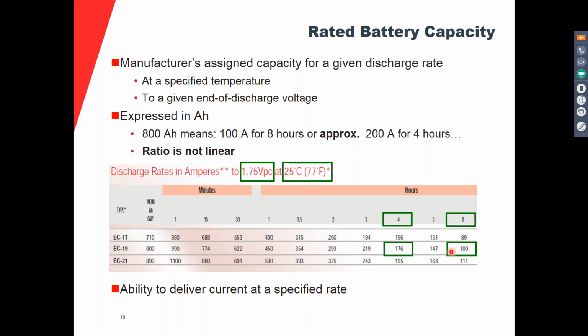You can see here with this example, for 8 hours, it can deliver 100 amps. So that will be 800 amp hours. However, for 4 hours, it can only deliver continuously 176 amps, which is less than a total of 800. So the tables have to be followed to be able to get the actual capacity. To get an accurate value, we need to follow the tables, and we need to be sure that the battery is operating at that temperature, and if not, we need to use a correction factor, and we're going to see that later on in the presentation. This rated battery capacity is also defined as the ability to deliver current at a specified rate.